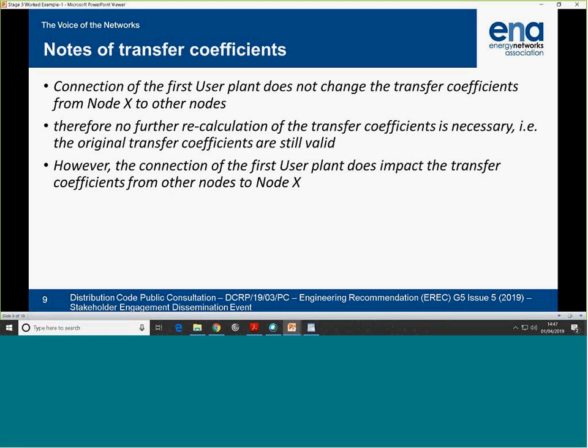There is a note in the document about transfer coefficients. The connection of the first installation does not change the transfer coefficient. As I said earlier on, the change in self-impedance and the perceived change in transfer impedance are the same. So the coefficient does not change. However, if you have connection to somewhere else, a capacitor or capacitor bank, then the story changes.